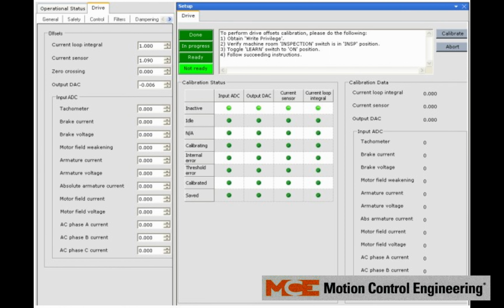First things first, you're going to want to make sure that your offsets are as close to 0 millivolts as possible on your SCR-LGA board on the drive. In the manual, it'll show you how to do an automated drive calibration and also how to manually do your drive calibration to read at close to 0 millivolts DC as possible from test points TP3 to TP18.